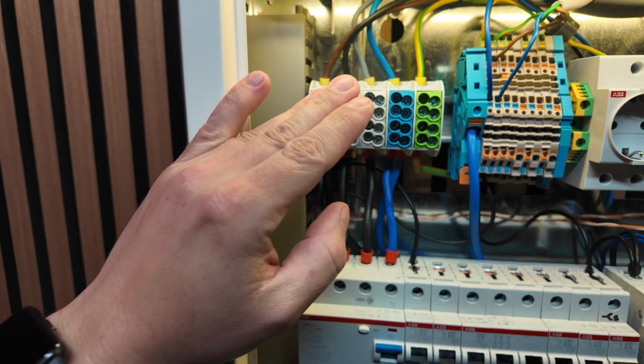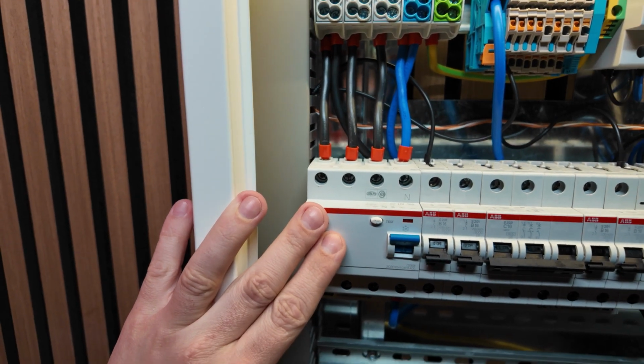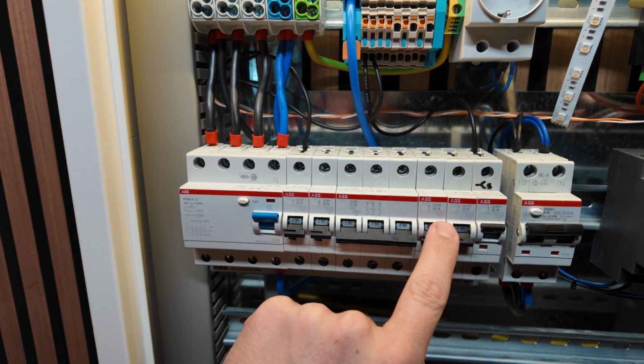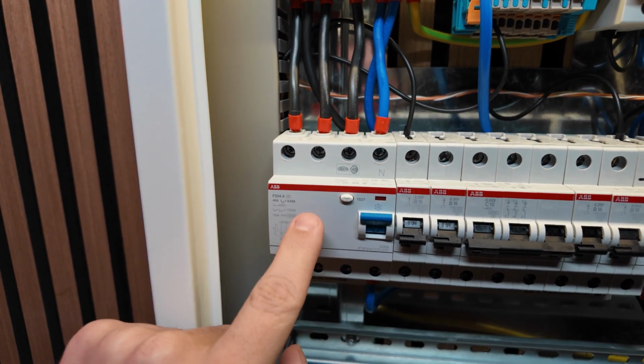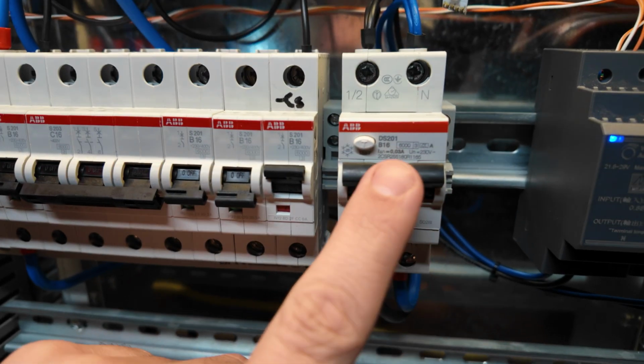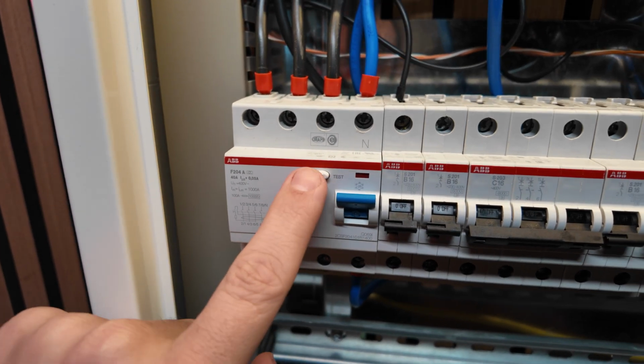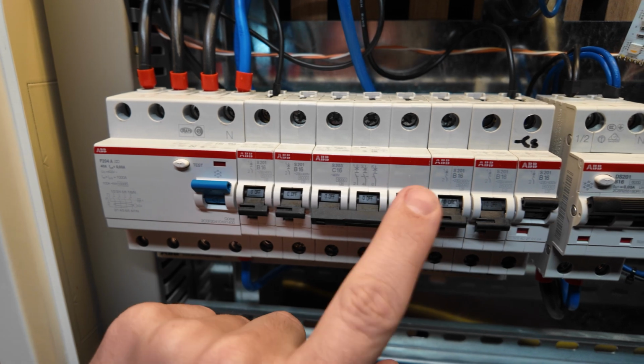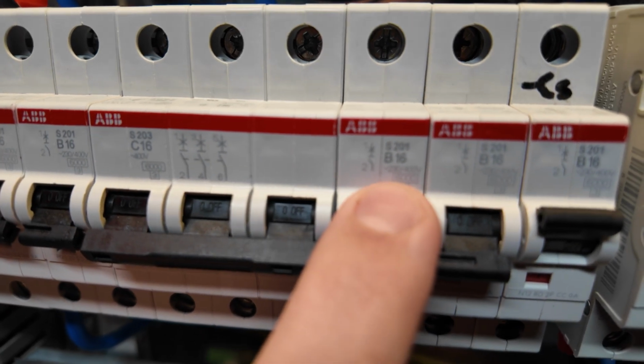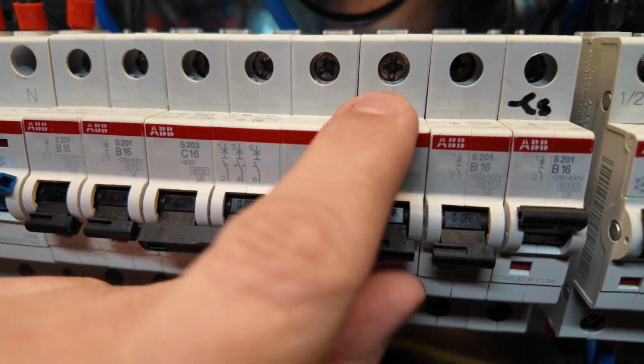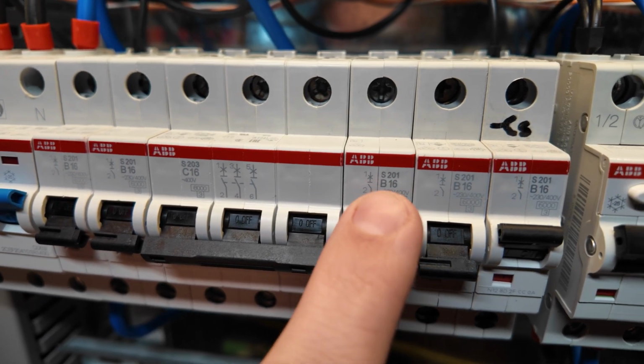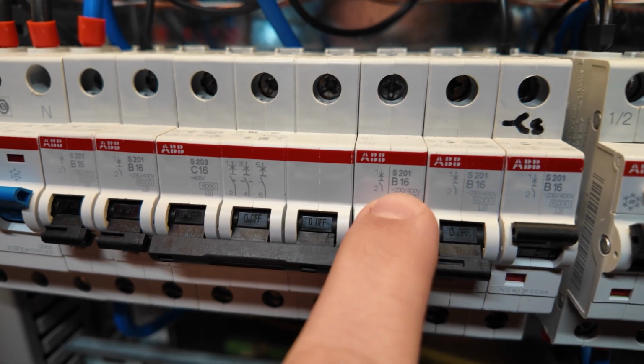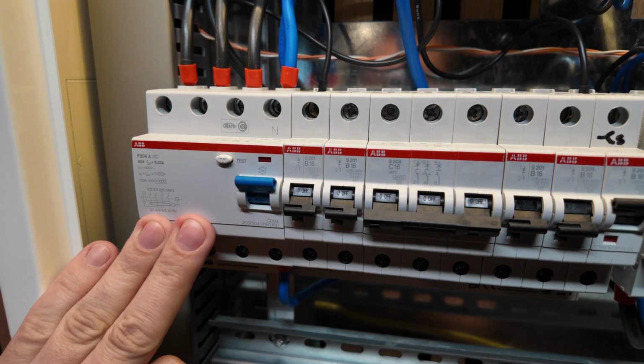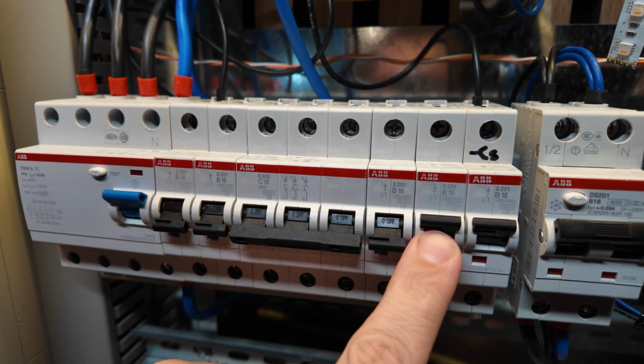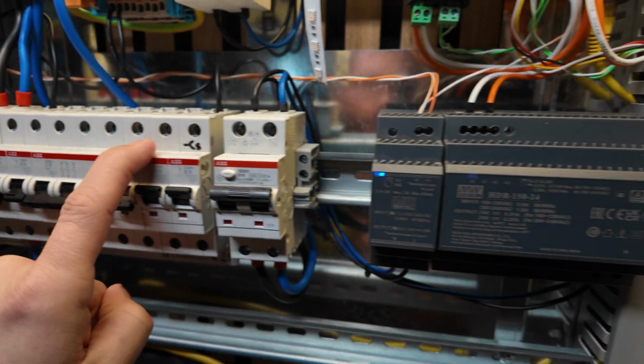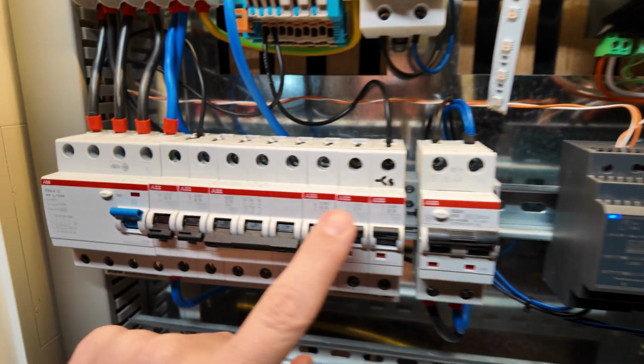From this main power coming in, we go onto our RCD, which has several breakers connected in my case. There might be countries where the breaker and the RCD are combined, like this device here. Here in Austria, the RCD is checking every single breaker, and the breakers themselves, for instance this one, B16, trip once the current is higher than 16 amp for a certain amount of time, depending on the characteristics. You could, of course, say one of the breakers, like this one here, is now used for the Loxone power supplies 24 volt. We have a look at this in a second.